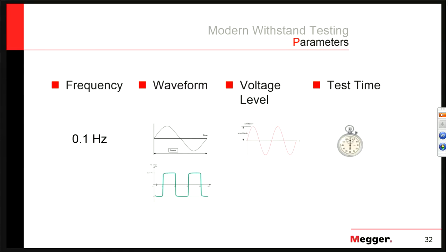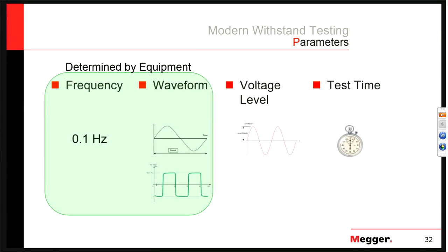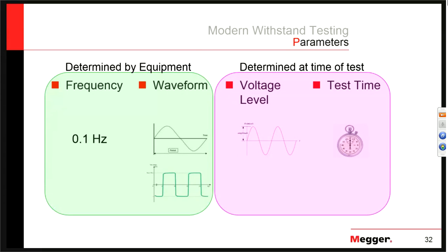The parameters of VLF tests are: frequency, voltage, waveform, and test time. Frequency and waveform are typically dictated by the equipment you get — they're going to be 0.1 Hz and either sinusoidal or cosine rectangular. That's a decision made at purchase time. The voltage level and test time are what you need to know at the time of the test, and they're based on where the cable is in its lifespan.